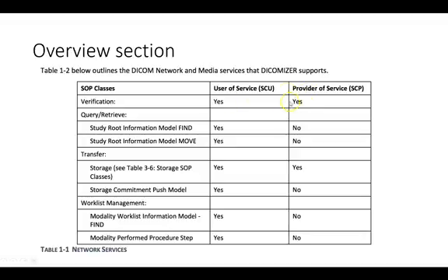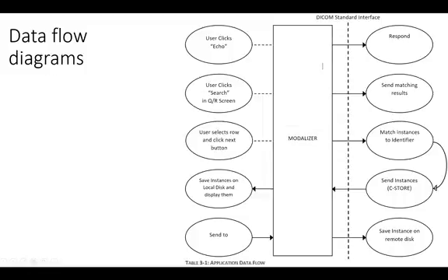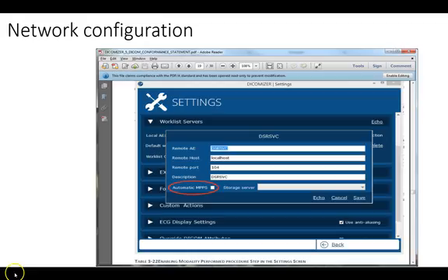Looking at this example — does this support C-Echo? Yes, right here I can see the Verification SOP Class as an SCU is supported. And as a provider? Yes, I can send or receive C-Echoes with this unit. Next is the data flow diagrams. This shows how the vendor imagines the data flow working. The circles on the left represent the action taken on the modality; the circles on the right represent what the vendor thinks the other application entity should do.